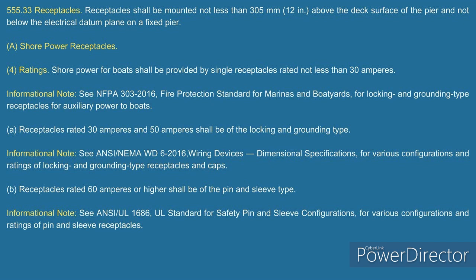You know what amazes me about this? If I'm plugging into that receptacle, why are they so specific, saying all my other receptacles have to have Class A GFCI protection, but when I go to the receptacle for shore power, it doesn't? But yet I'm going to allow to have my GFPE protection at the equipment or the feeder upstream. Yeah, and that's a good point, James.